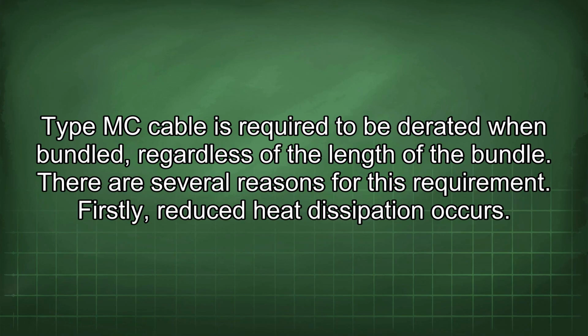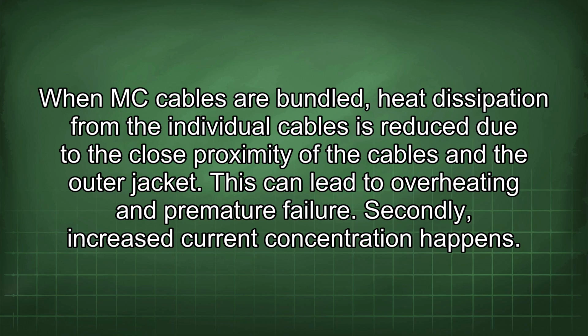Type MC cable is required to be derated when bundled, regardless of the length of the bundle. There are several reasons for this requirement. Firstly, reduced heat dissipation occurs. When the MC cables are bundled, heat dissipation from the individual cables is reduced due to the close proximity of the cables and the outer jackets. This can lead to overheating and premature failure.